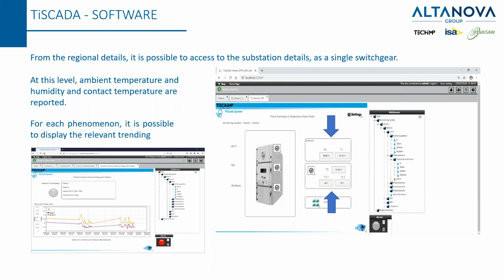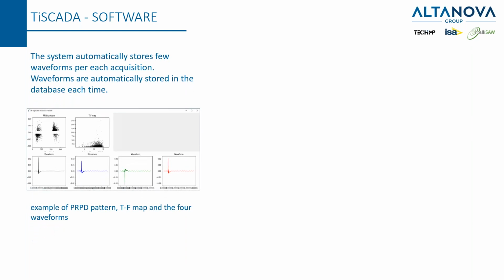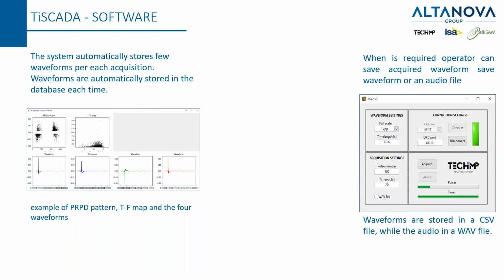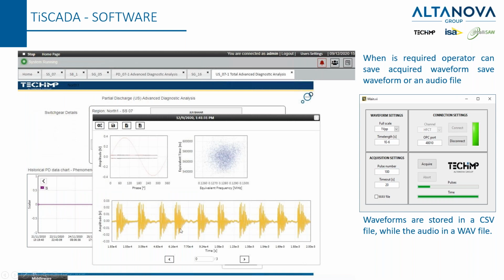For each phenomenon, also in this software, it is possible to display the relevant trending. A few other words about the SCADA. The system automatically stores a few waveforms, basically 4, per each acquisition. Waveforms are automatically stored in the database each time. These are 2 examples of PRPD pattern, TF map, and the 4 waveforms. When required, the operator can save the acquired waveform or audio file. The waveforms are stored in a CSV file, while the audio files are in a WAV file. This is how the audio file and the waveform saved inside the SCADA look.